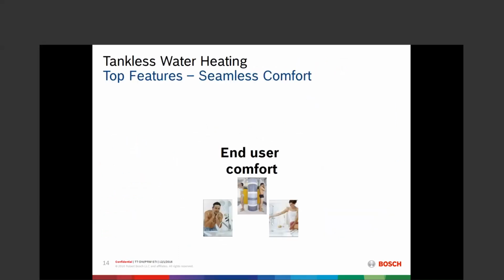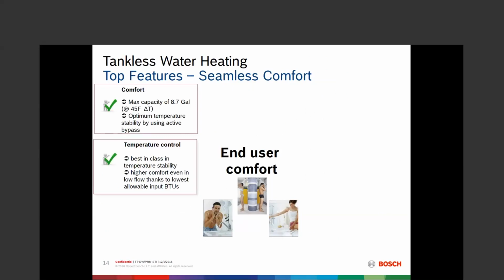So ultimately, who has to be happy with this product is the end user. The end user has to be comfortable. So we give very, very high flow rates due to the efficiency. Very, very stable temperature. We're using what we call an active bypass as part of our controls, which gives us very, very good control over our temperature stability. Activation flow rate at 0.45, so 0.45 gallons per minute flows through the unit. The burner is light. Then that can be turned down to a flow of 0.35 after the burner is light.